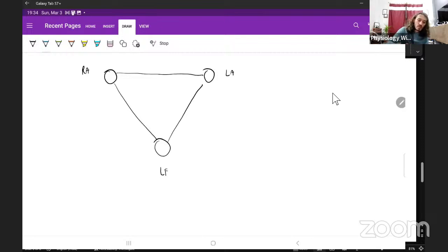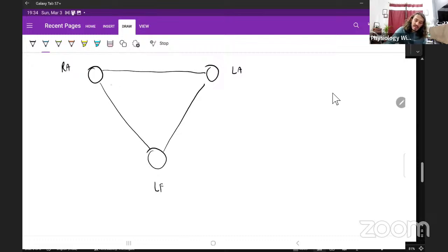So what we're going to do is create a near zero potential. To do that, we take impulses from here, connect to a very high resistance, around 5000 ohms, and connect it to a central terminal like this. So take high resistance and connect them all to a point in the center. This point in the center will act as your reference, which is your inactive electrode.